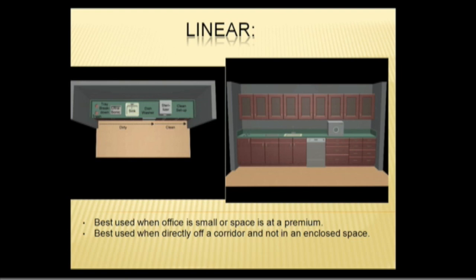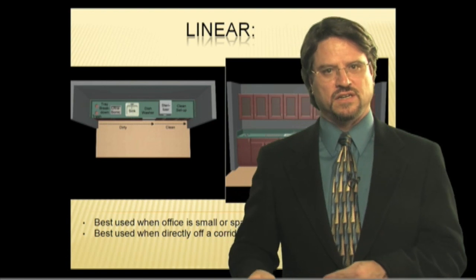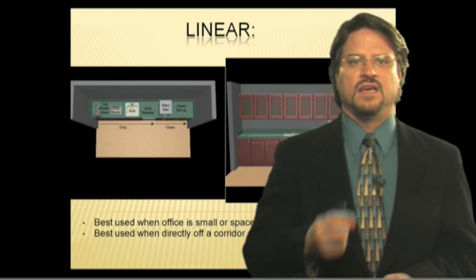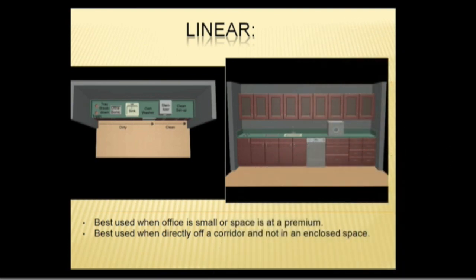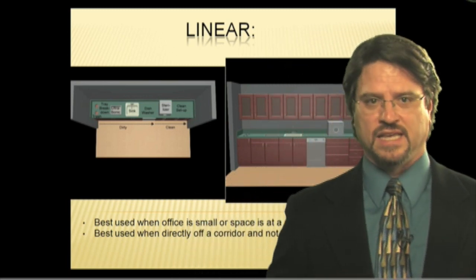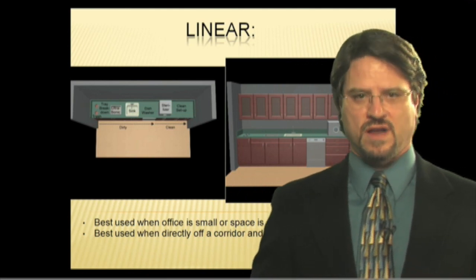In general, all sterilization should be designed to support the flow of contaminated to sterile. You'll see on this graphic the counter work surface, provide for tray breakdown and trash receptacles for contaminated trash and sharps at the beginning of the process. The ultrasonic cleaner is next after breakdown, and the sink, which is next, typically marks this demarcation between contaminated and sterile. Although if an under-counter dishwasher or instrument drying before autoclaving is used, it may be placed adjacent to the sink. Alternatives are an ESMA unit, which is an ultrasonic with a dryer on top, a full instrument washer like a Miele, or at a minimum provide a countertop drying area.